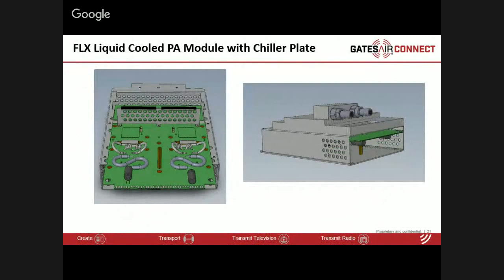The nozzles you see in the right-hand picture are quick-seal, quick-release disconnects. They're sort of like hose faucets with a pin, and when the pin of the receiving coupler goes into the center of that hose coupler, it pushes a valve in. It's a spring-loaded valve that cuts off the flow on both sides of the connector.